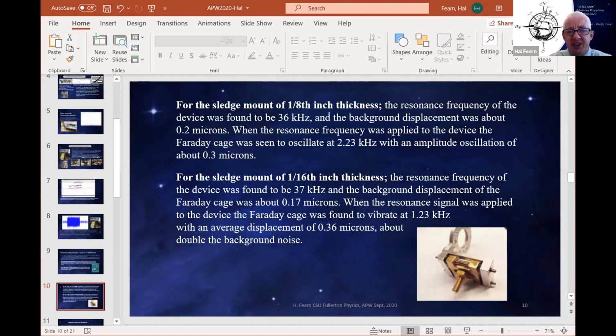And with the 1/16 of an inch thickness of this mount bracket, it was 0.36, so maybe slightly greater, but the vibrational frequency went down. It went down to 1.23 kilohertz rather than 2.23 kilohertz. So again, it's nothing to do with the 34 or 35 kilohertz that I was seeing as resonance. It's a smaller frequency, and the displacement was very, very small. But again, if I were to shine the vibrometer directly at the beam, you literally see nothing at all. You see the background. Even when the thing is on resonance, you don't see anything transmitted at all because the yoke is so good at vibration isolation. So I just thought I'd mention that.